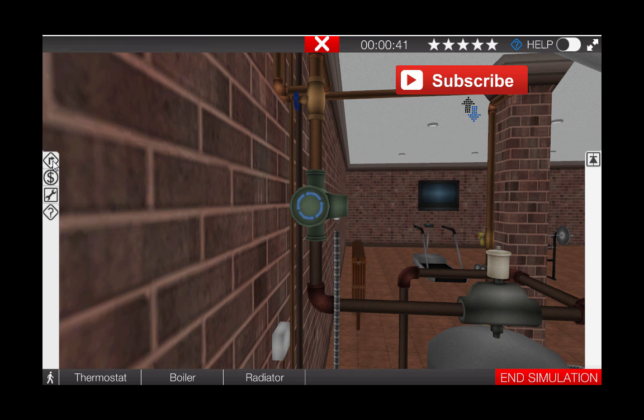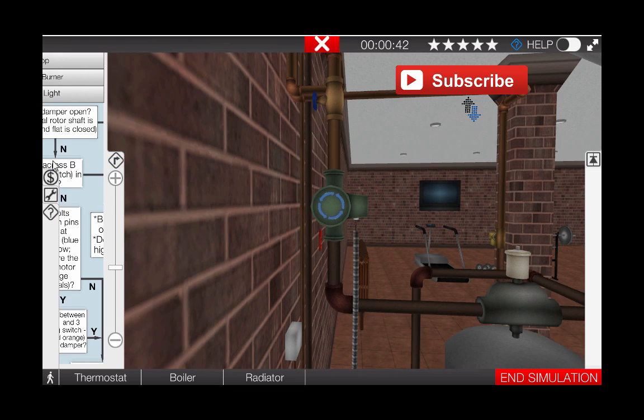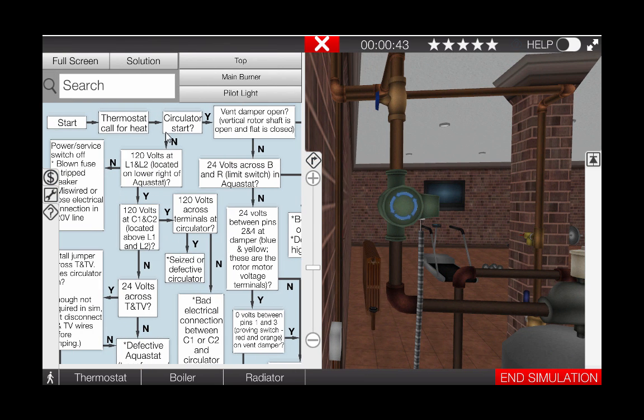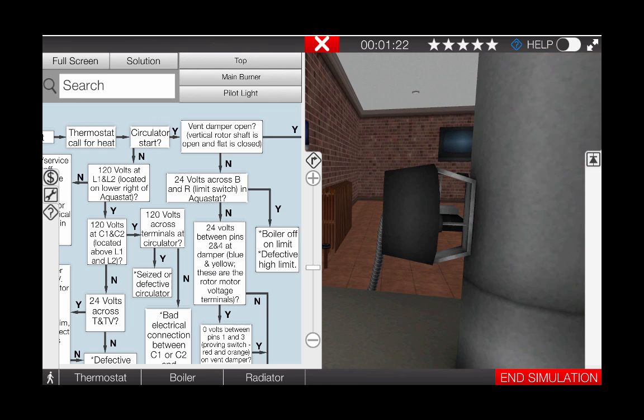Consulting the troubleshooting flowchart by clicking the tab on the top left of the page, we can see that after seeing that the circulator is started, our next step is to verify that the vent damper is in fact open.